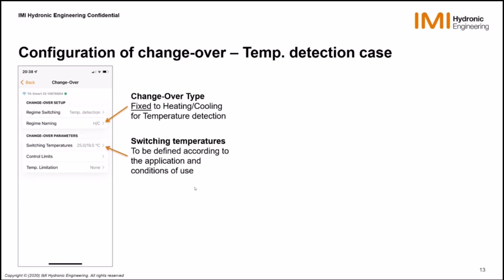The switching temperatures have to be defined according to the application and the conditions of use. The default values, I have set them like this: 25 degrees for heating. So I need the water to be warmer than 25 degrees to decide that I am in heating. I need the water to be lower than 19 degrees to decide that I am in cooling. Why so high a switching? Simply to be generic enough. If you do cooling ceilings, you might have a 16, 18, even a 17, 19 degrees type of regime. And therefore we have to be a little bit careful with that. Obviously, you can change these values to adapt them to the situation of use in the application.